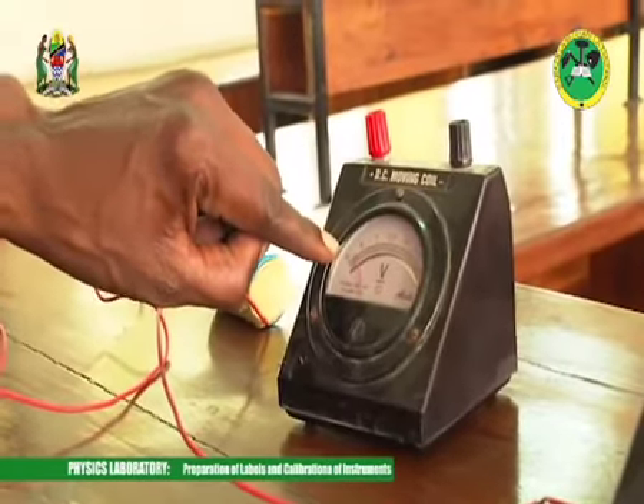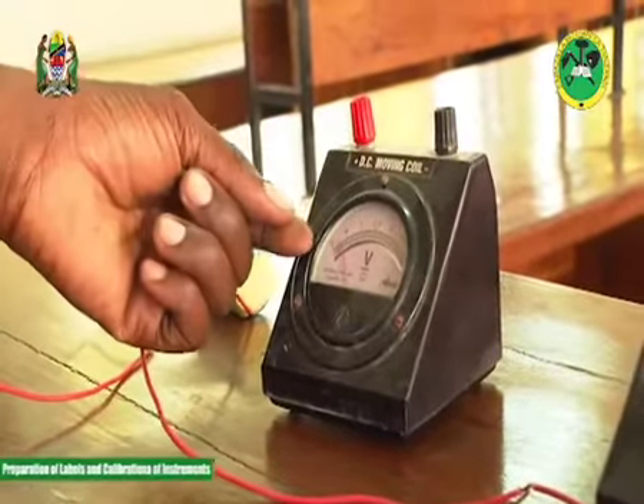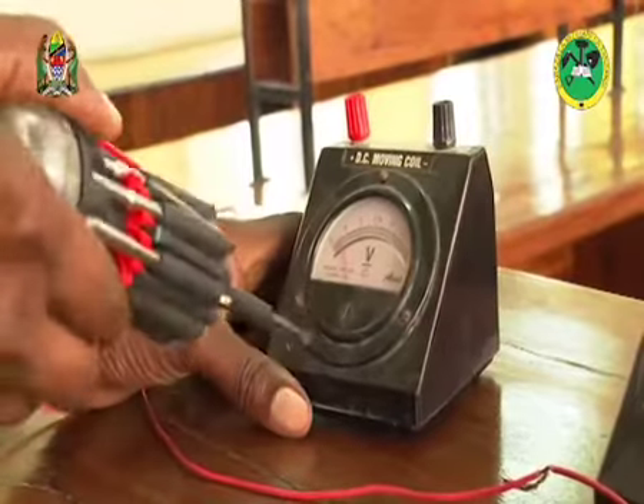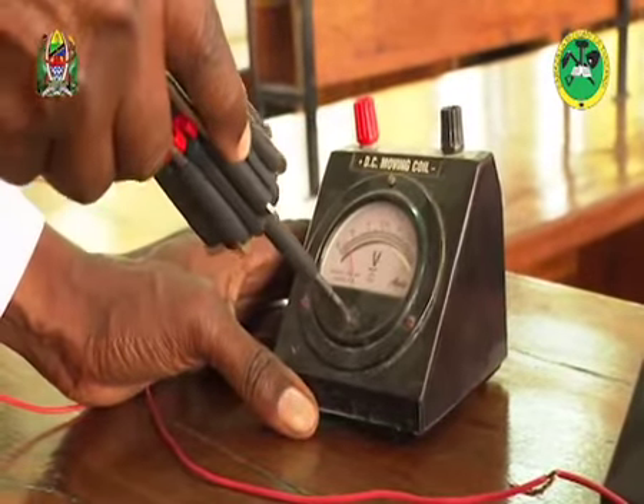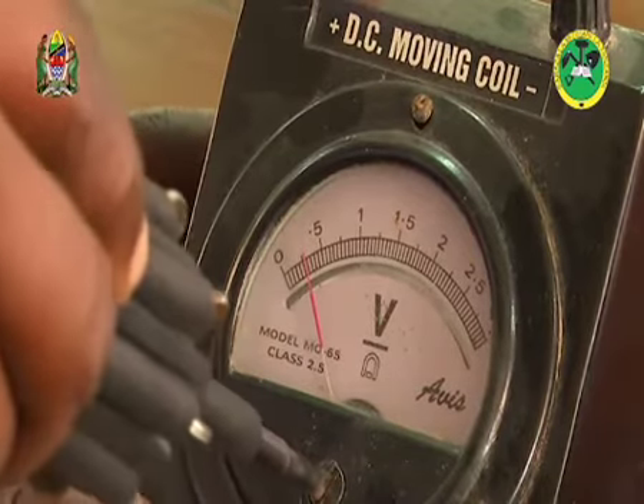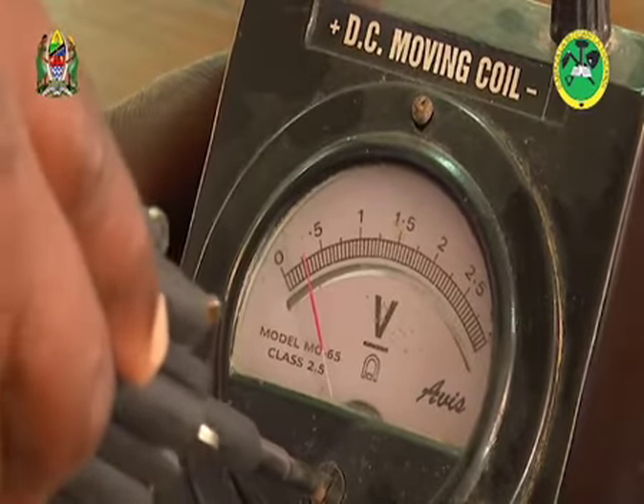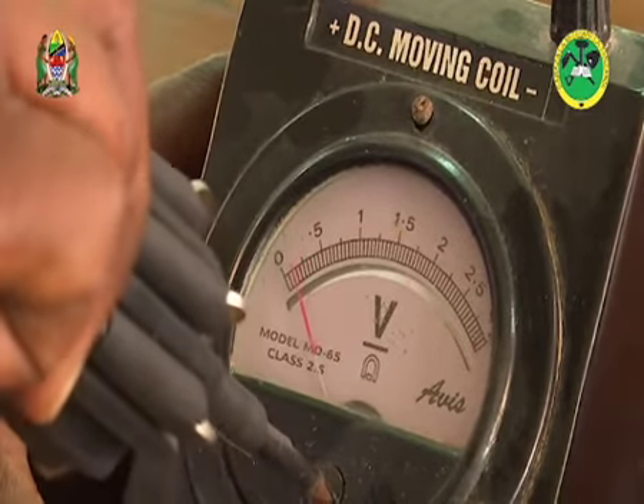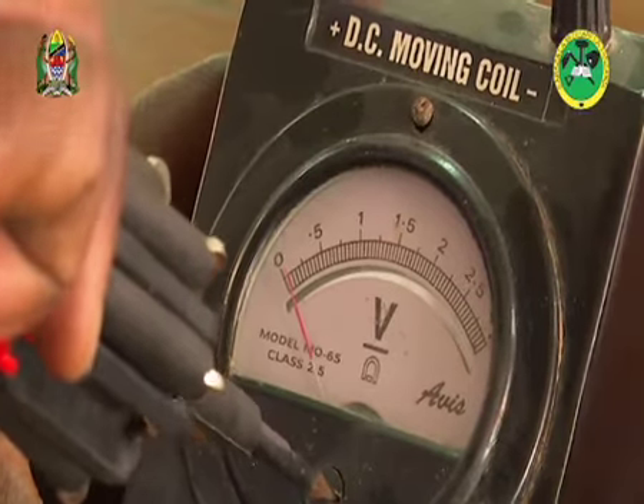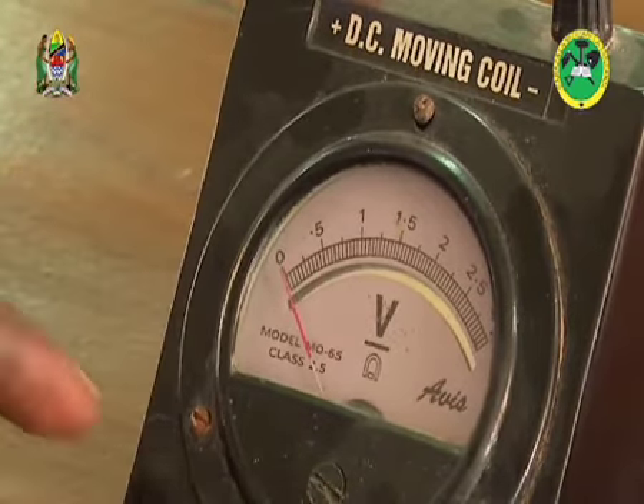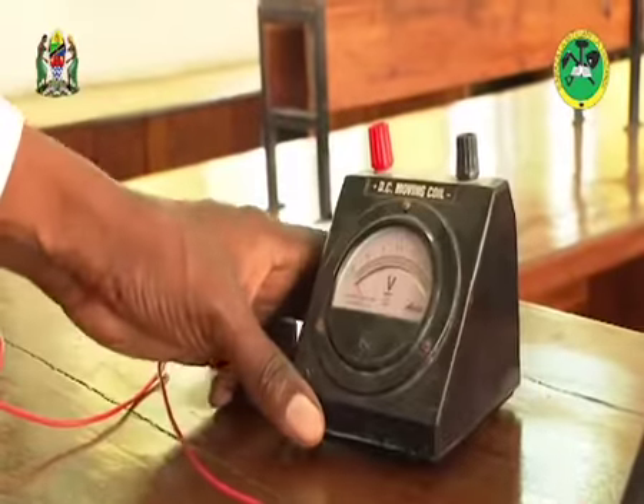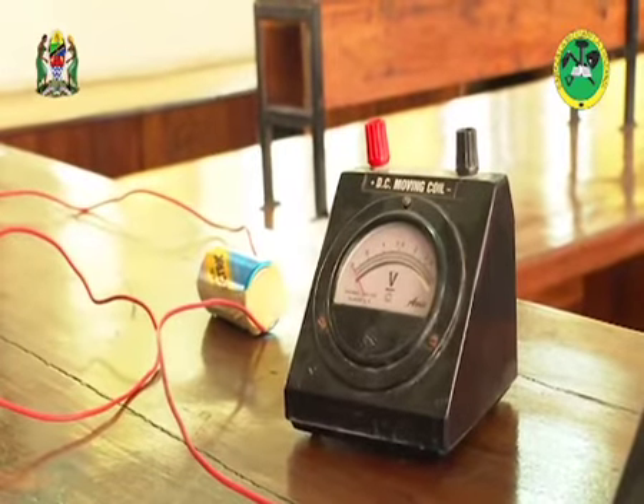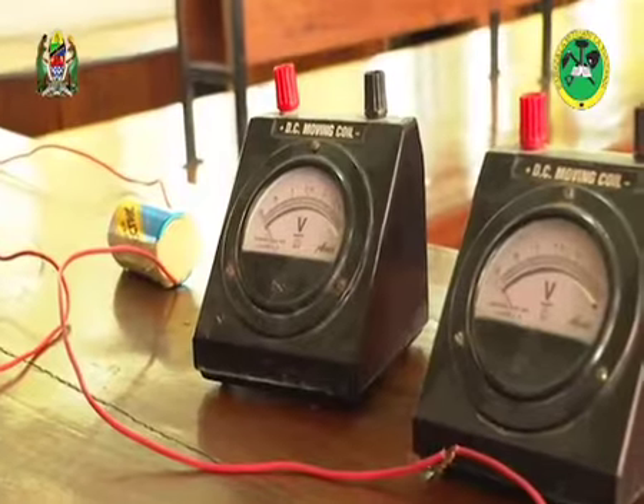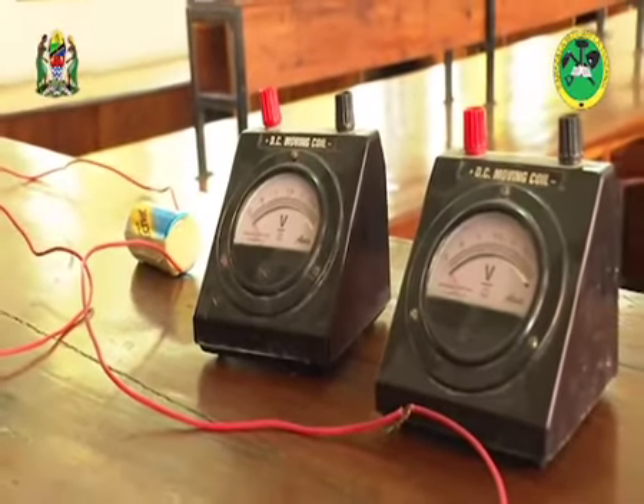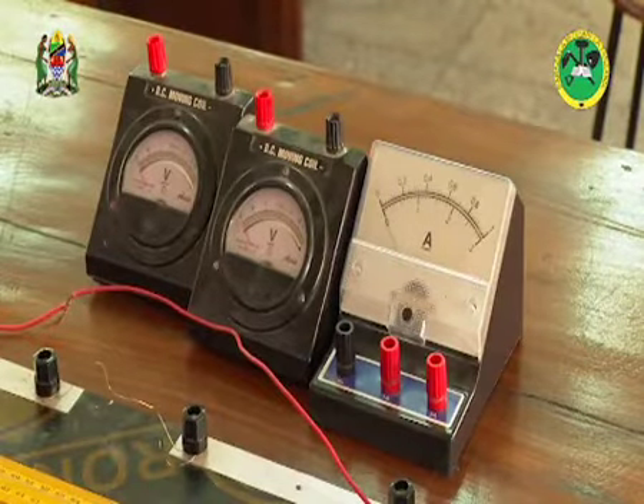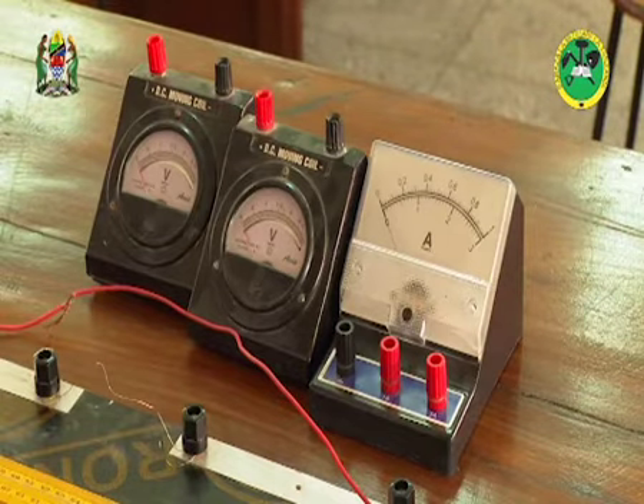So the best way to do it, because this has gone a bit forward after the zero mark, is to adjust it counterclockwise this way. Now you can see you take it back to the zero position. Make sure that it is pointing exactly at the zero position. There, exactly, and check if it is exactly at the zero. There. Now you can see it is pointing at the zero mark correctly, just like this one here. Now here you can take the reading. Now that was the part on correct zero error adjustment.